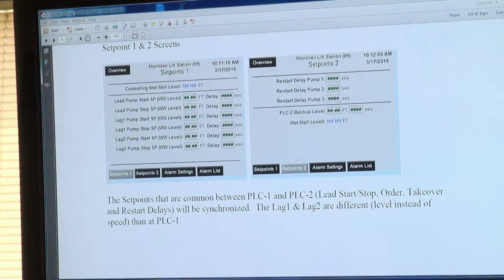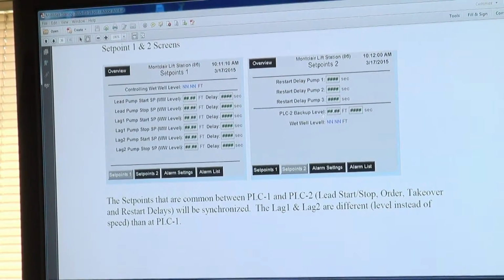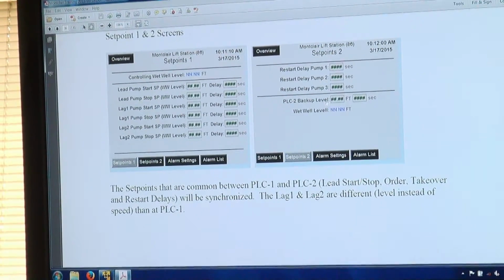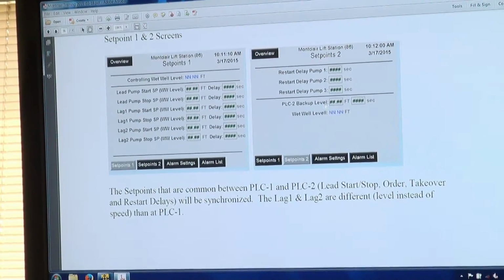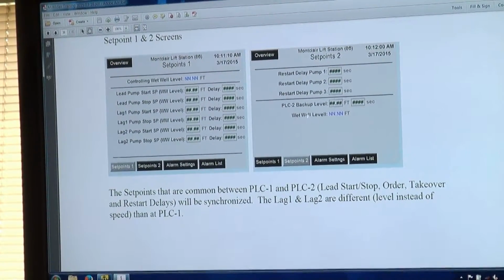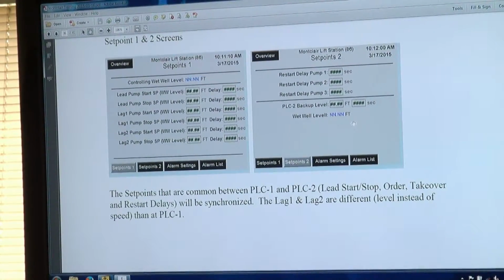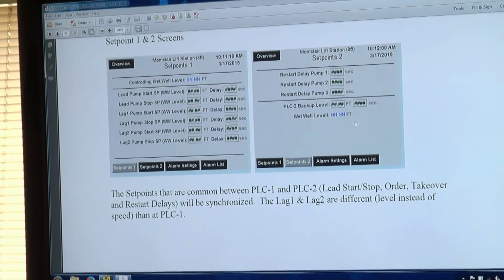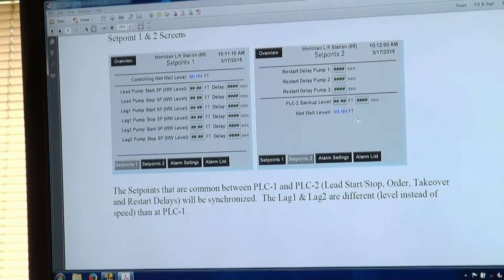The second one is, again, your 3 minutes between starts, and then what level is it going to take over? So we have it at 6.4, which is your high level, or 6.2, just below that, so that we can try to take over. We did try once we were up and running to start at a higher level than what we currently have. It's very close to not recovering at a peak time. We get 1 pump started, we get 2 pumps, but that level just kept rising. So be careful raising the start level as well back at PLC 1.